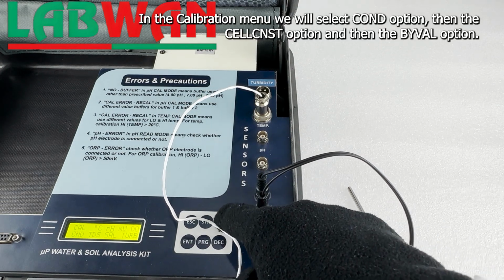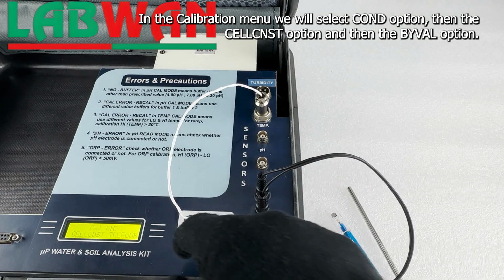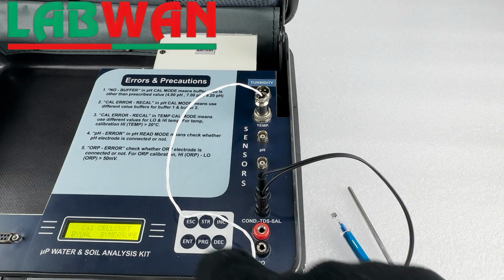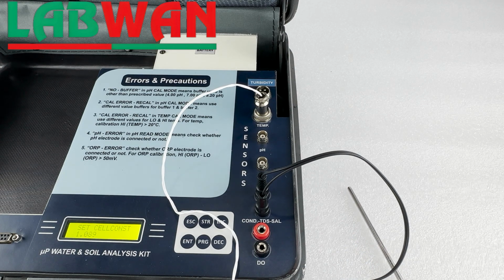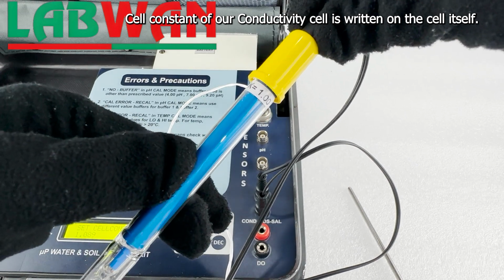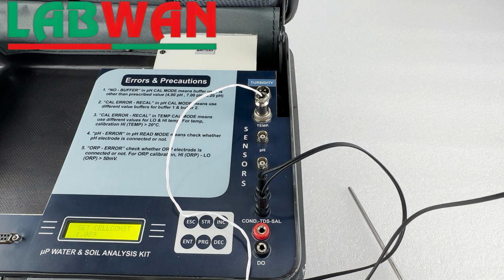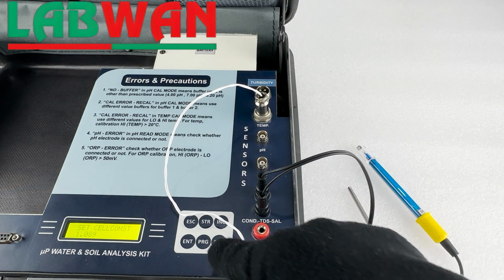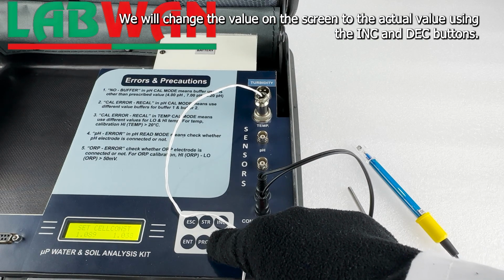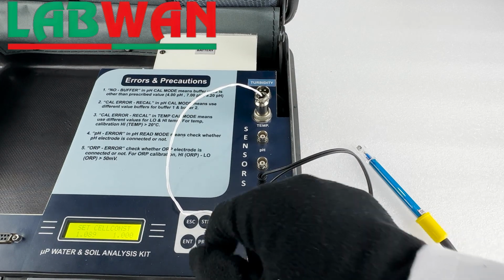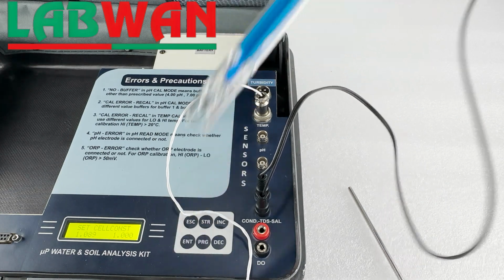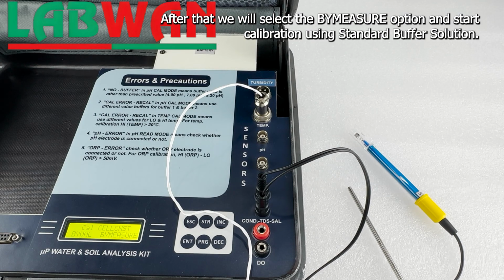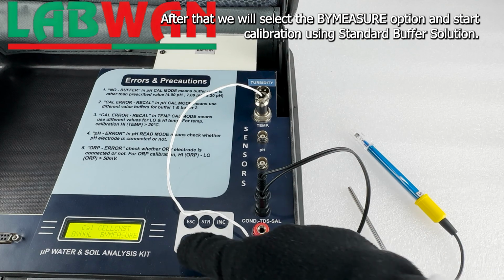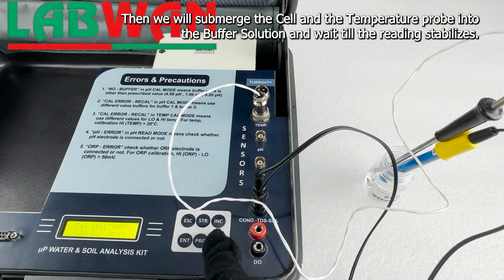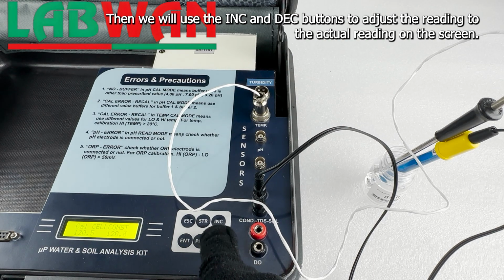In the calibration menu we will select COND option, then the cell CNST option and then the by VAL option. Cell constant of our conductivity cell is written on the cell itself. We will change the value on the screen to the actual value using the INC and DEC buttons. After that we will select the By Measure option and start calibration using standard buffer solution. Then we will submerge the cell and the temperature probe into the buffer solution and wait till the reading stabilizes. Then we will use the INC and DEC buttons to adjust the reading to the actual reading on the screen.